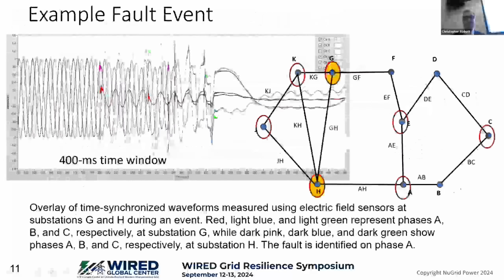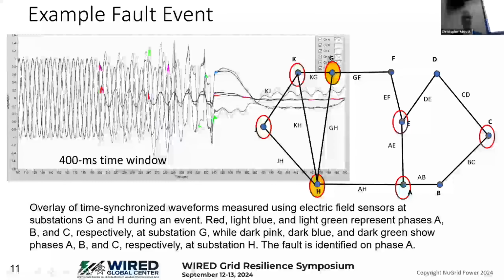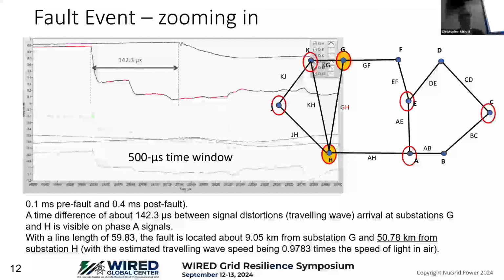An example: a fault happens between substation H and G. You can locate it based on the time difference between those. I zoom in on this waveform, just this little portion—this is 400 milliseconds, about 24 cycles worth. But if you zoom into a half-millisecond version, you can look at the time difference of those pulses arriving. The traveling wave concept again is not new, but the implementation is practical and quick. It says, hey, it's about 9 kilometers from substation G.